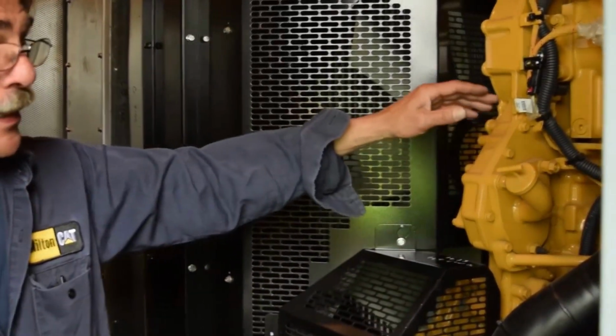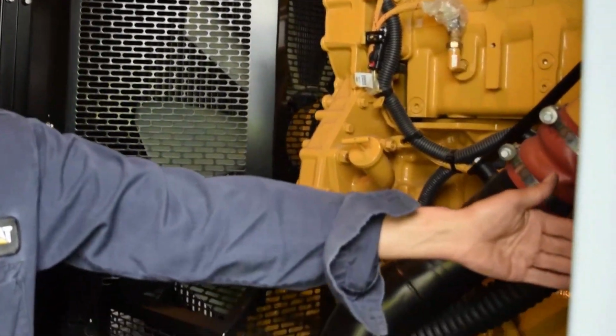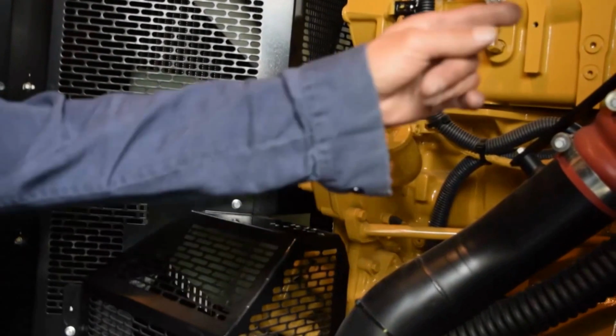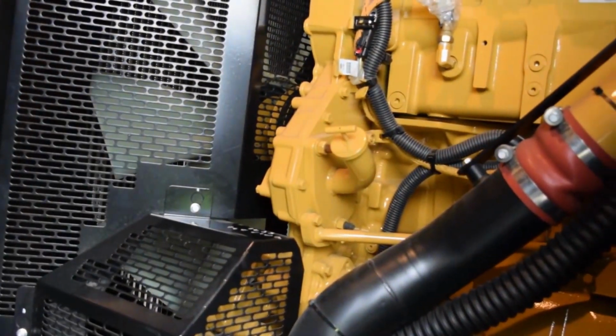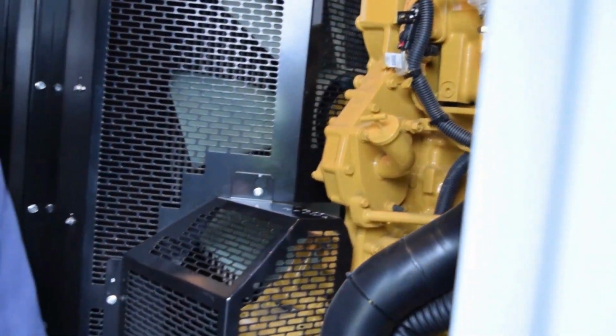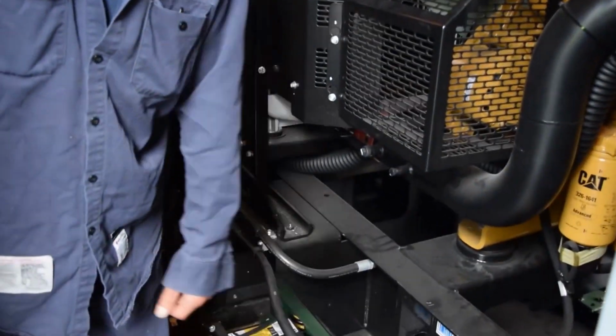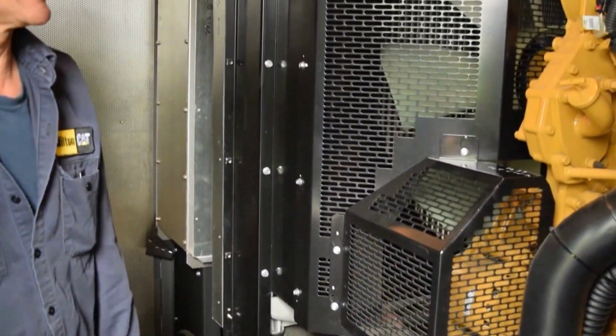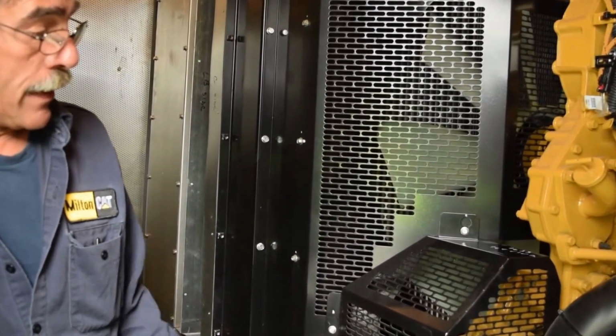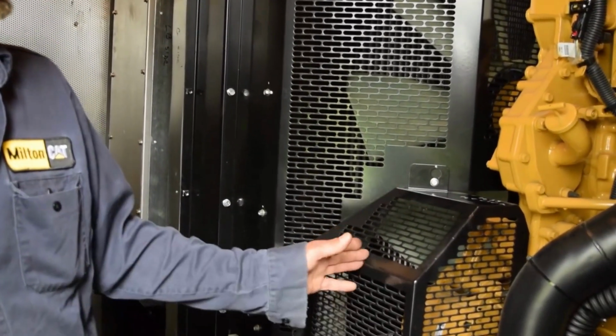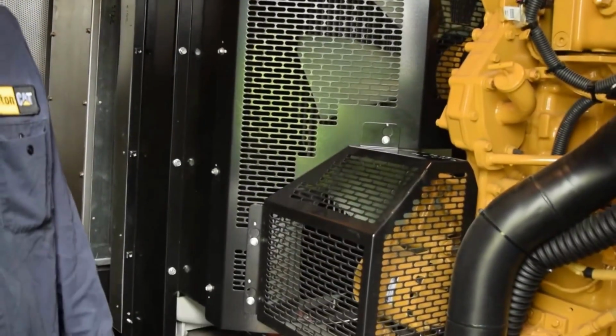Up in this area we have our oil fill, we have the dipstick hiding right around the corner, the fuel filter hiding right around the corner, our batteries, and our battery switch where we can shut the batteries off during the lockout tagout procedure so we can be disconnected. Our primary fuel filter, our alternator, and our fuel transfer pump.